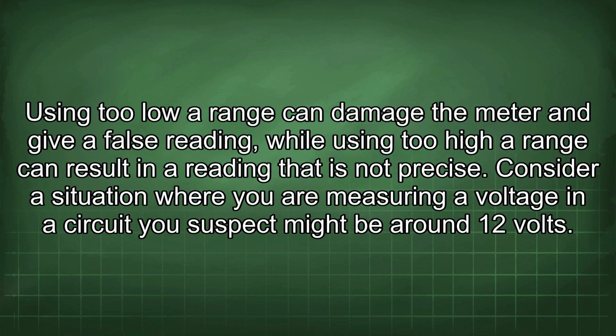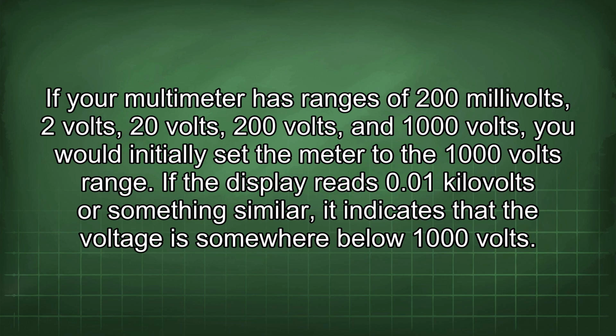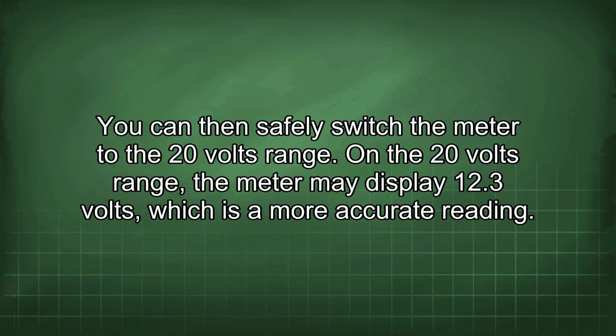Using too low a range can damage the meter and give a false reading, while using too high a range can result in a reading that is not precise. Consider a situation where you are measuring a voltage in a circuit you suspect might be around 12 volts. If your multimeter has ranges of 200 millivolts, 2 volts, 20 volts, 200 volts, and 1000 volts, you would initially set the meter to the 1000 volts range. If the display reads 0.01 kilovolts or something similar, it indicates that the voltage is somewhere below 1000 volts. You can then safely switch the meter to the 20 volts range.